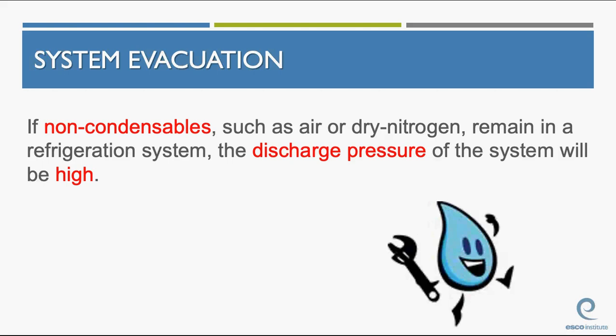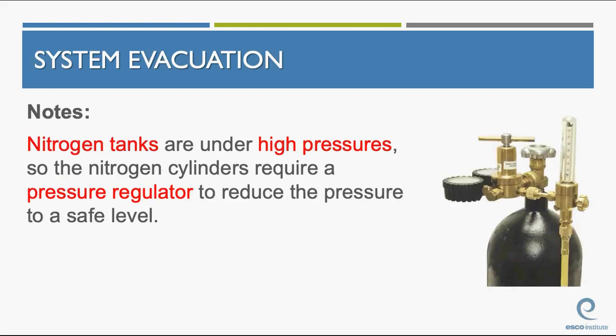If non-condensables such as air or nitrogen remain in a refrigeration system, the discharge pressure of the system will be extremely high. This is another slide. You need to know this entire slide. I think this is on page 23 of your book or something right around there. If non-condensables such as air or dry nitrogen remain in a refrigeration system, the discharge pressure of the system will be high. It will look like an extremely dirty condenser. And even if the condenser is clean, it's still going to act like a dirty condenser. Those non-condensables get stuck at the top of the condenser. They can't condense.